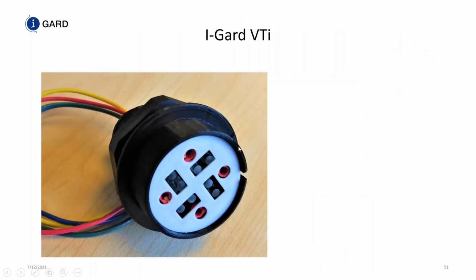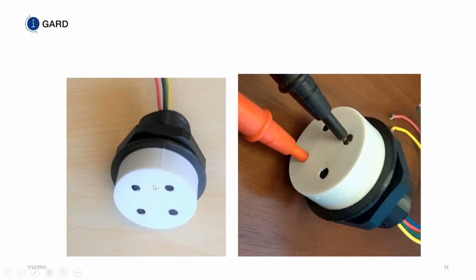But if you do like the voltage test station, we've developed another product which provides in one unit voltage portal, voltage indication, and you can monitor the voltage on the system with this device. When the system is completely intact, we have this cover on there.